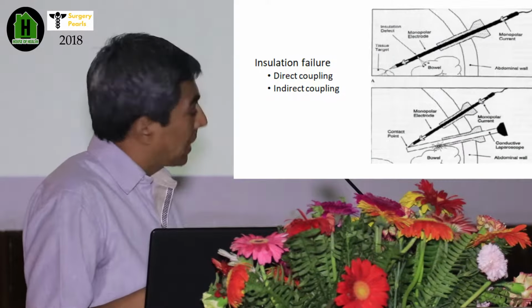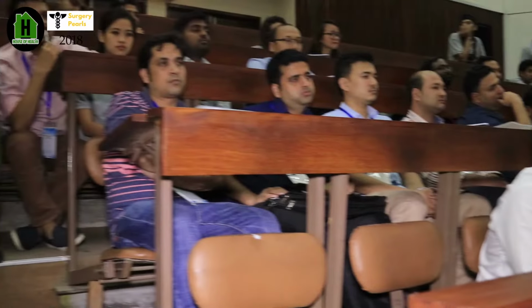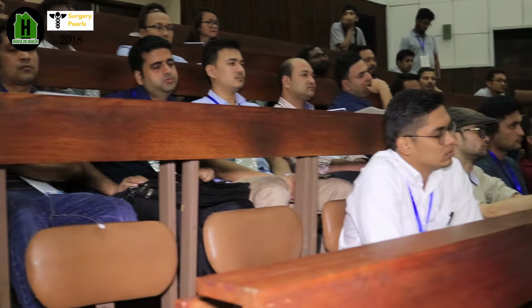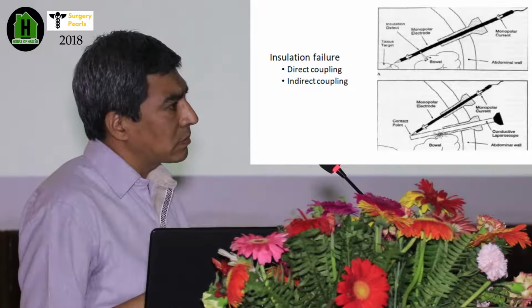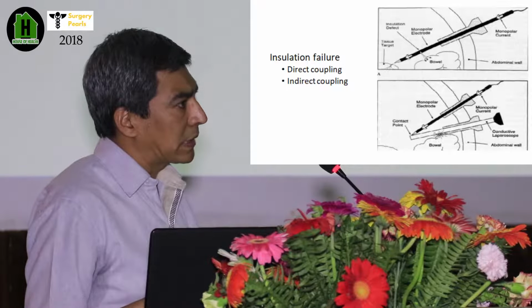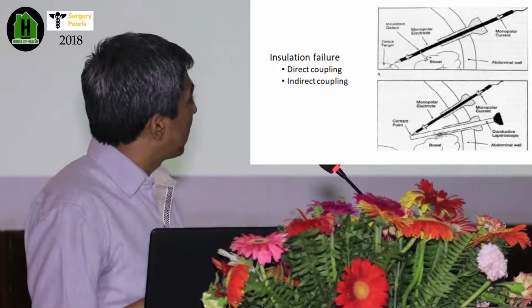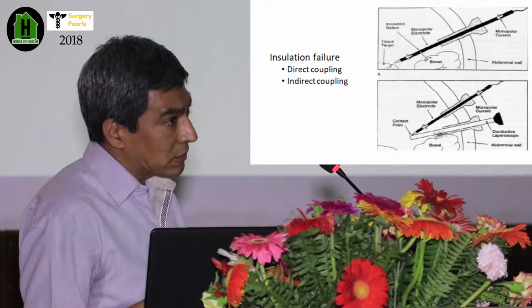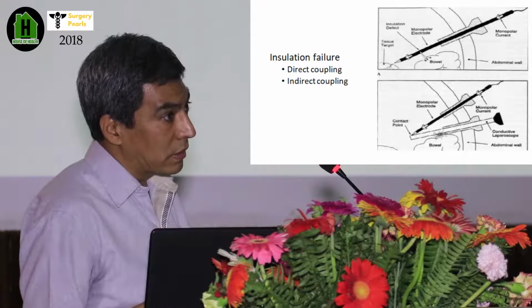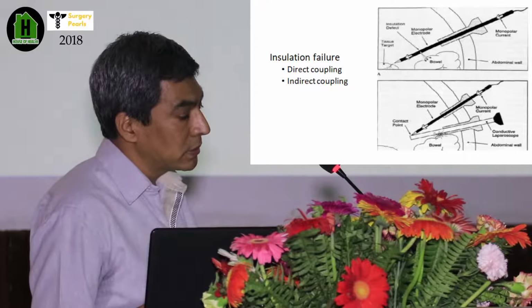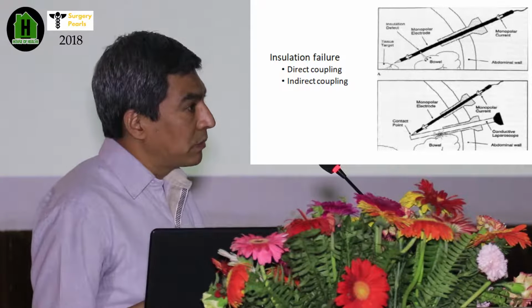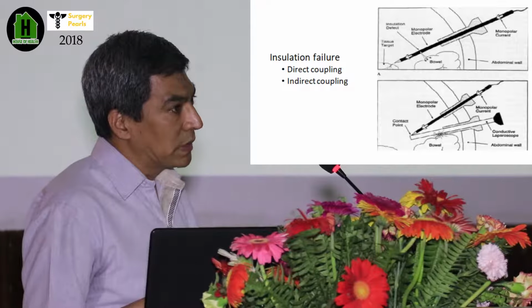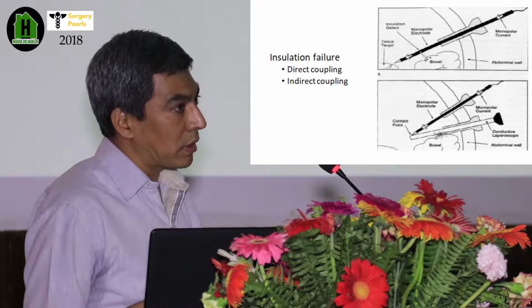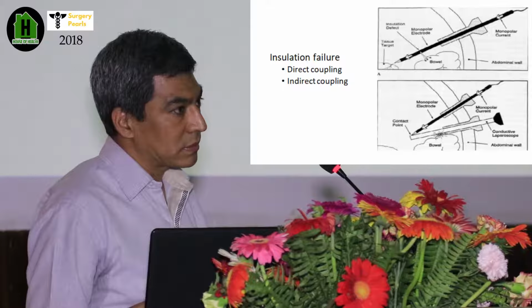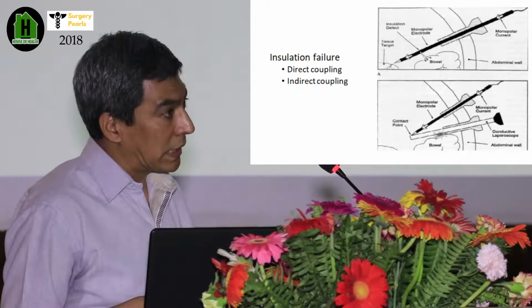So I try to make it clear with these pictures how direct coupling happens. This is your laparoscopic device. Those are things you can see most of the time in laparoscopic surgery rather than in open surgeries. So this is a laparoscopic instrument. If the insulation of this instrument is breached somewhere, small holes, we won't know that. From there, the electricity will leak and transmit to the adjacent structures, causing burning or a cutting effect without the surgeon knowing. That is called direct coupling.